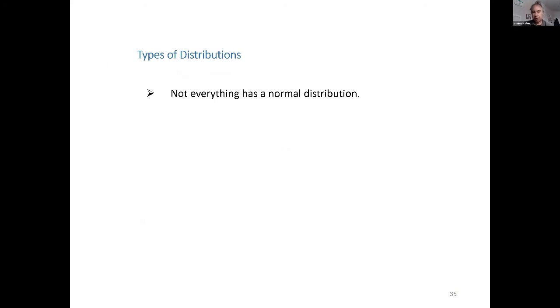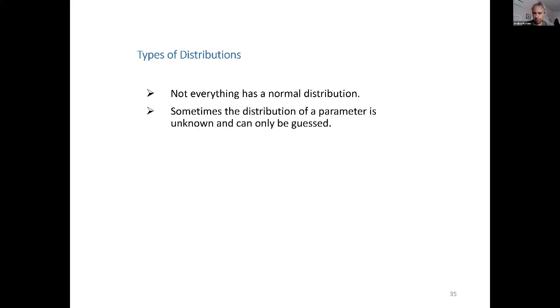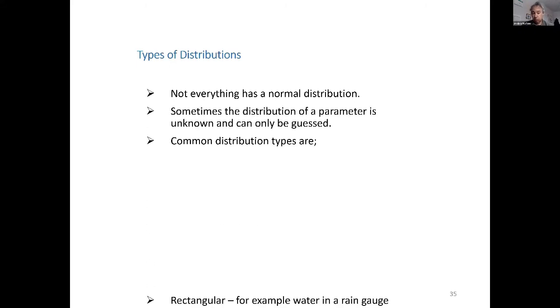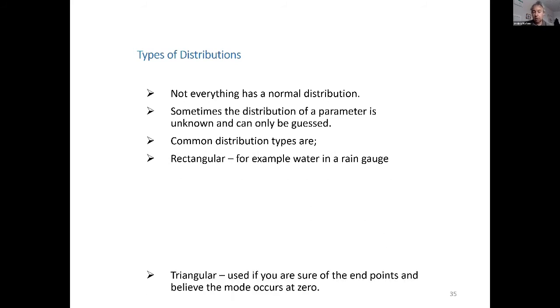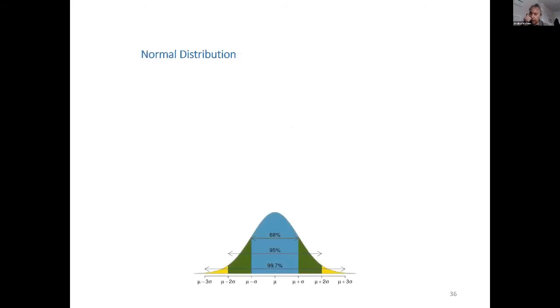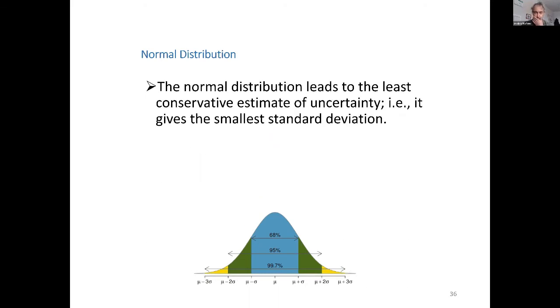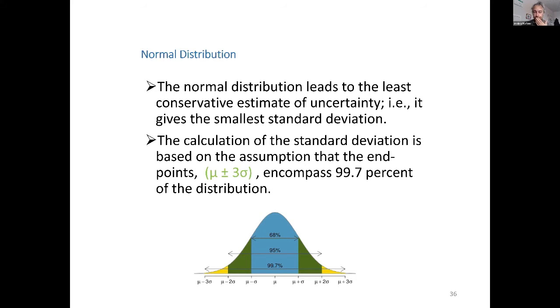We have different types of distribution. Not everything is a normal distribution. Sometimes you don't know. And we have the normal, the rectangular, and the triangular. The normal distribution is the one you know. So hopefully at the end of your analysis, the overall uncertainty is normally distributed, but it comes from not normally distributed terms. Okay. If you add 3 sigma, you go to 99.7%. Normally, we add the value plus 2 sigma in order to have 95% of your representativity.